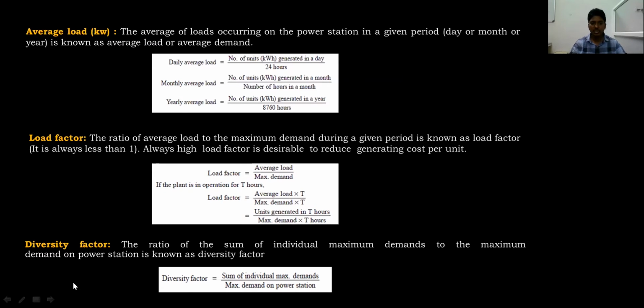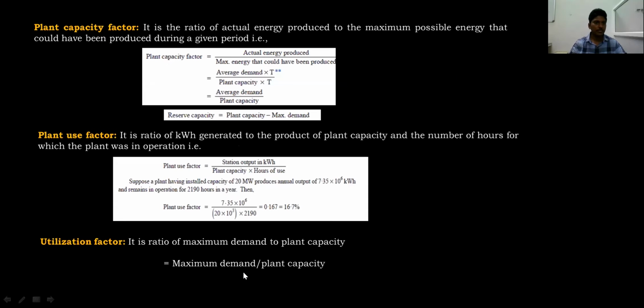Diversity factor: the ratio of the sum of individual maximum demands to the maximum demand on the power station is known as diversity factor. And plant capacity factor: the power generated by the plant divided by the power it can generate in all 365 days. This ratio is known as plant capacity factor. Here we consider the actual energy produced. For example, out of 1 year, it has produced some X units, but it can generate more than what it has generated.